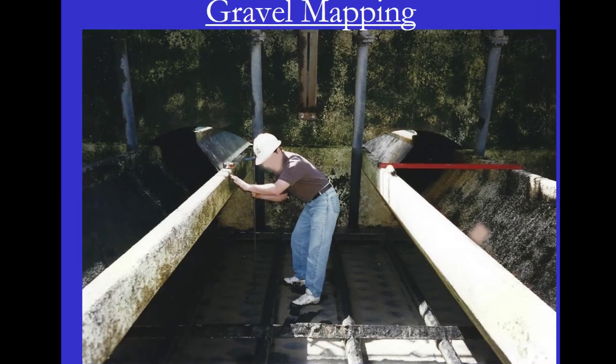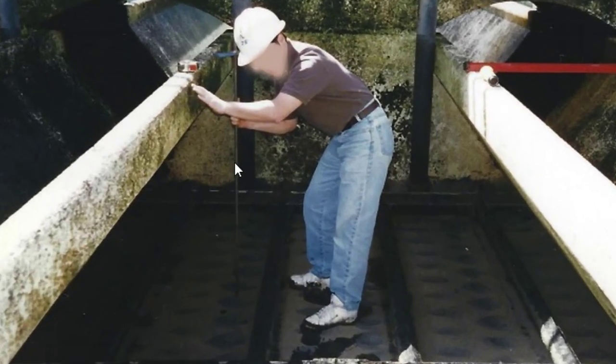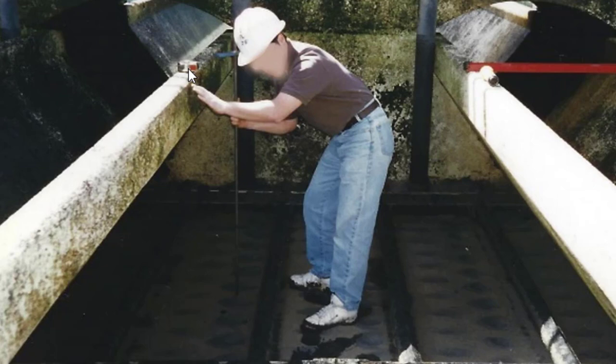The way a gravel mapping tool works — here's one here, which is actually a pin rod from the distribution system. You put the gravel mapping tool into the media and the media makes a certain sound. As it hits the gravel, it makes a different sound — it kind of rings. You grab the mapping tool right at the interface with the media, pull it up, and then with a tape measure, measure the distance. Do this at various locations in the filter to determine how level the gravel is.